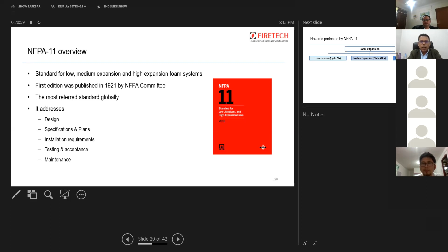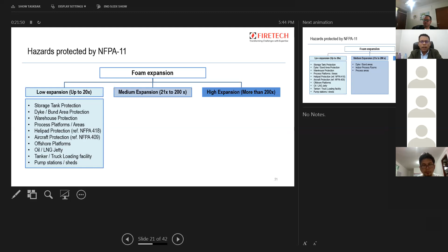So again, let's review what hazards are protected by different types of foam systems based on the expansion values. The first is the low expansion foam systems. They are used for oil storage tank protection. Not only oil, it can also be for polar solvents like methanol, ethanol, alcohol storage tanks. Dike or bund area protection, that is for protecting the space in case of a spill fire around the tank dike, around the tanks. Warehouse protection, process platforms and areas, helipad protection, aircraft hangar protection, offshore platforms, oil and LNG jetties, then the oil tanker or truck loading facilities, and hydrocarbon pump stations or sheds.